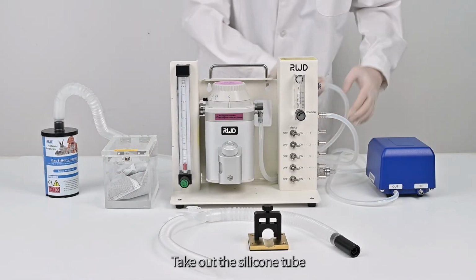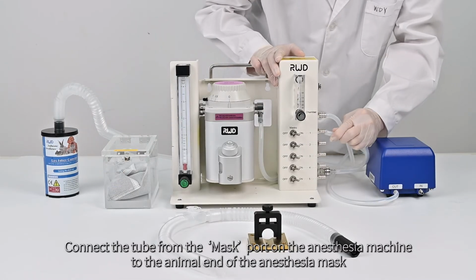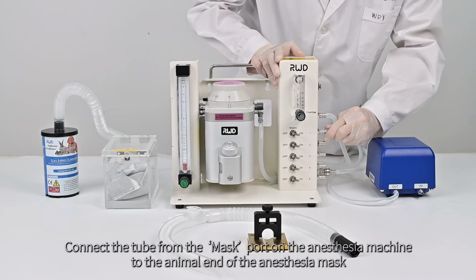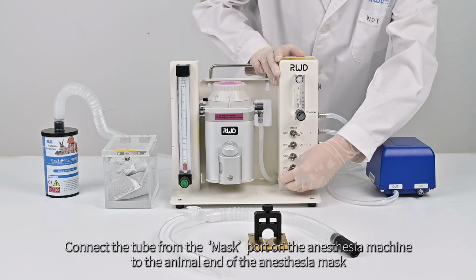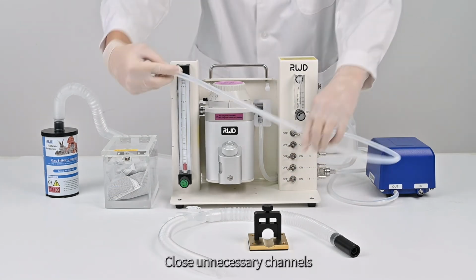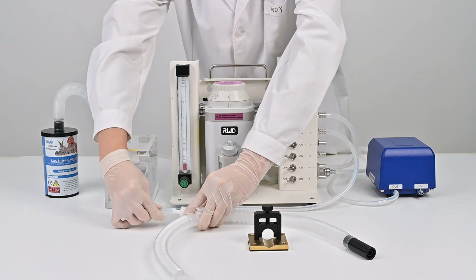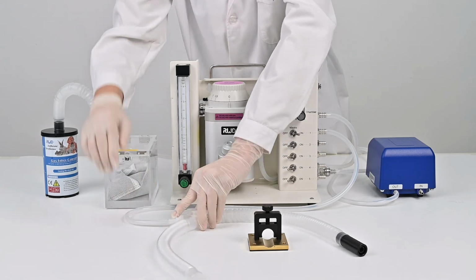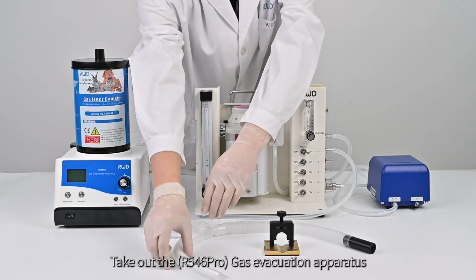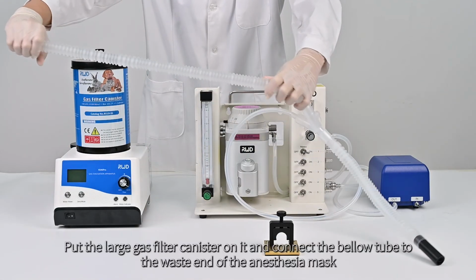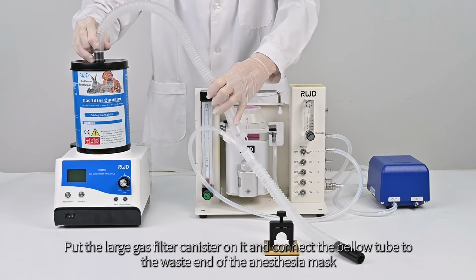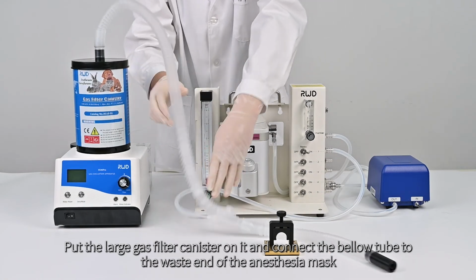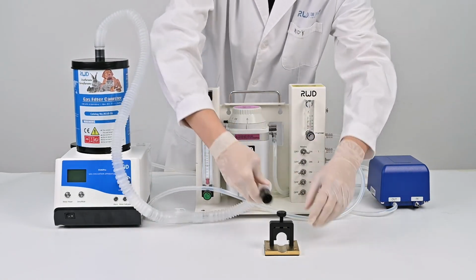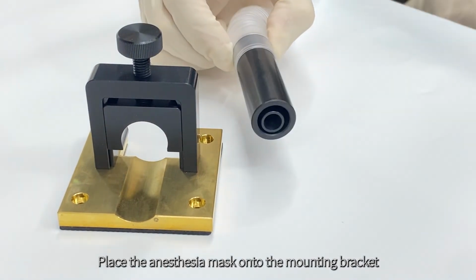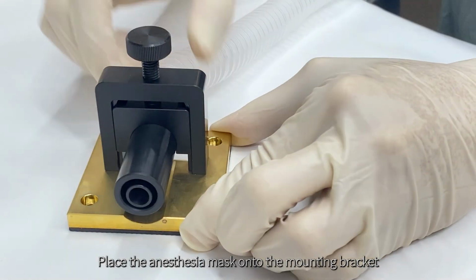Take out the silicone tube. Connect the tube from the mask port on the anesthesia machine to the animal end of the anesthesia mask. Close unnecessary channels. Take out the gas evacuation apparatus, put the large gas filter canister on it, and connect the bellow tube to the waste end of the anesthesia mask. Place the anesthesia mask onto the mounting bracket.